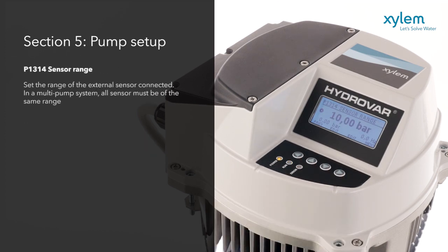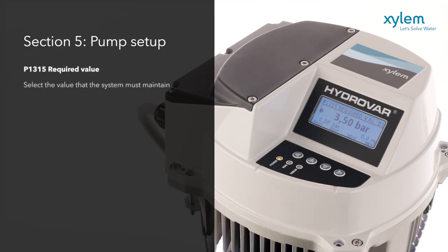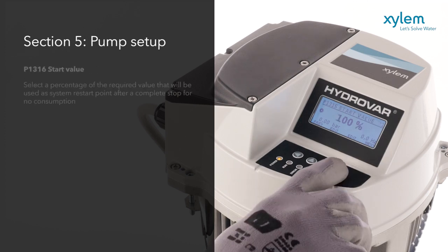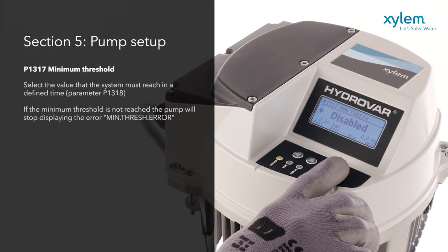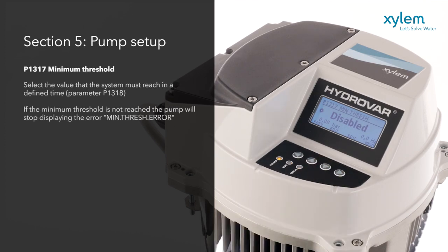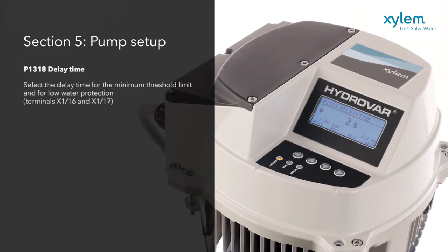Select and calibrate the sensor prior to the system going live. Set the required pressure in the system. Choose the starting point for when pressure drops and the minimum threshold for the pump to turn off when pressure or flow does not make duty within a set time. Similarly, delay times and water protection thresholds can be set.